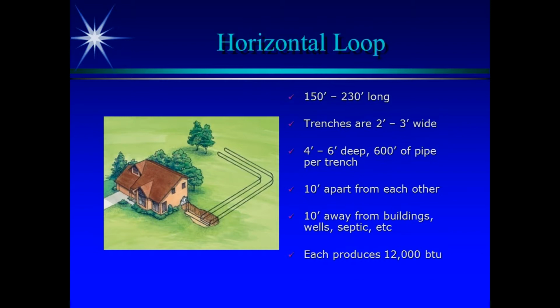If you've got a heavy damp clay, that's a really good soil that's easy to work with. If you've got a dry sand, it's harder to work with. We can still do it, but we use a lot more pipe to get the same amount of BTUs out of there. So these trenches typically are 2 to 3 feet wide, 4 to 6 feet deep. And typically in that type of configuration, there's 600 feet of pipe in that trench. These trenches are 10 feet apart from each other.